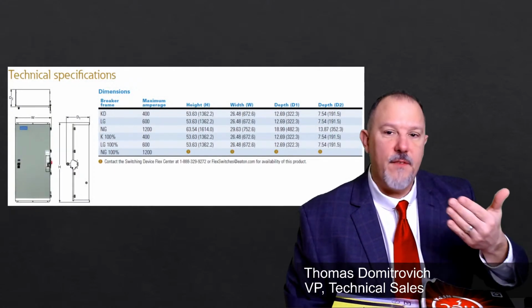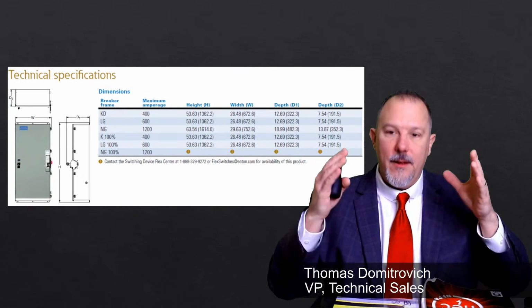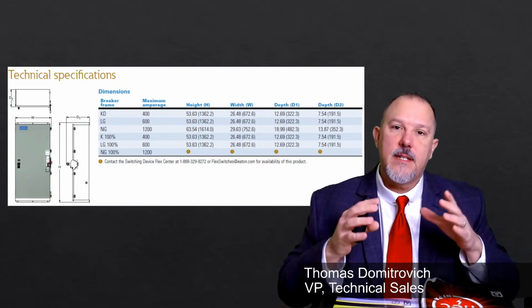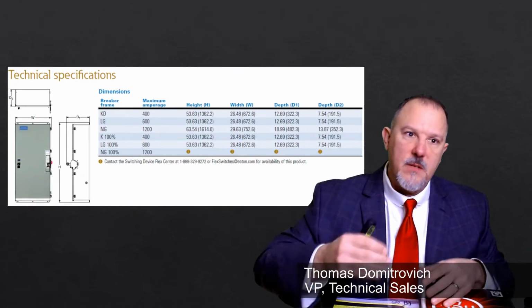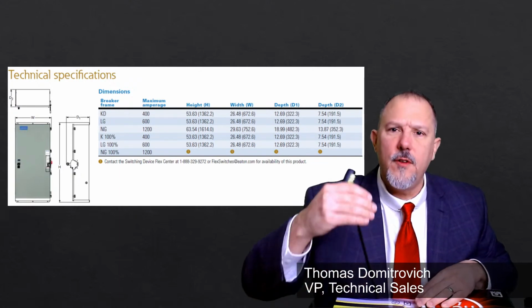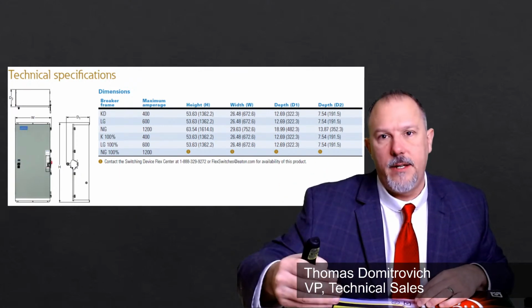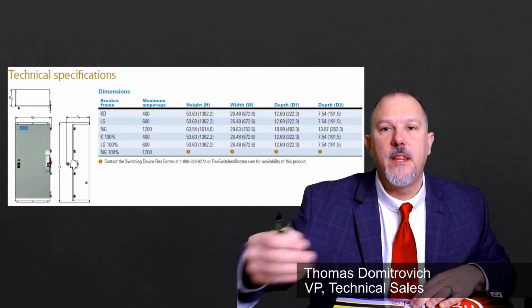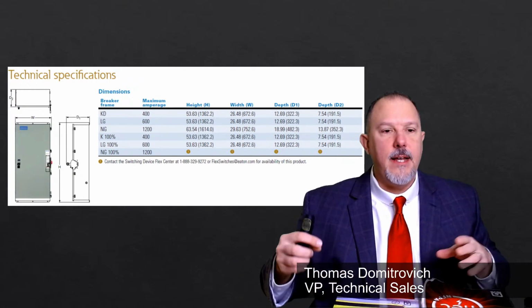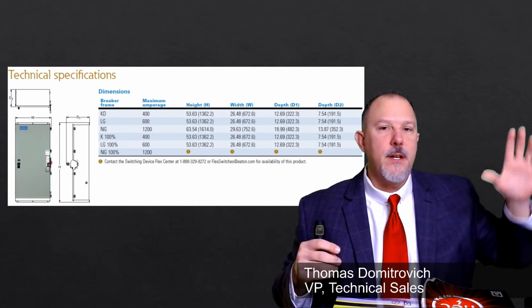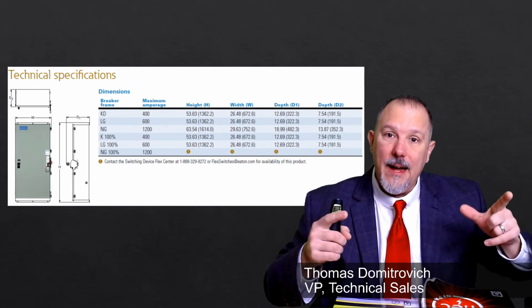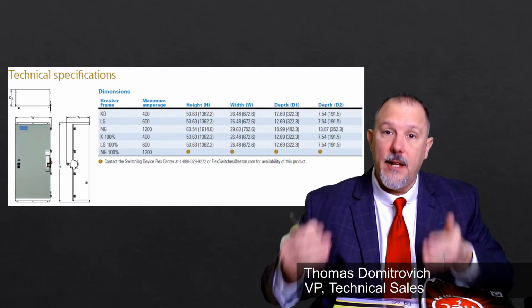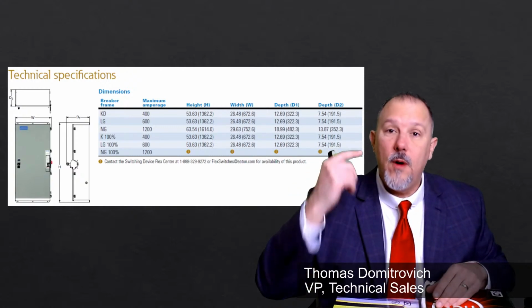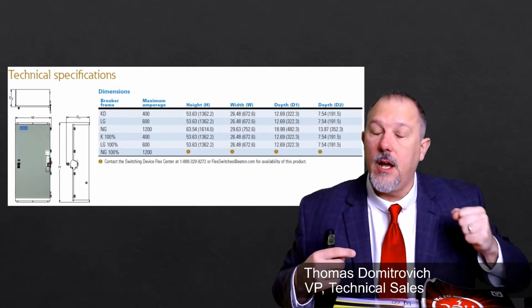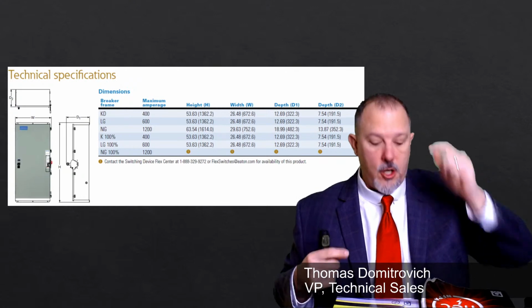All right, we have the enclosure size. The reason I put this in here from a size perspective: put these products as close as you can to the equipment you're trying to provide the protection for, right? If it's a panel board, try to put it next to the panel board. Why? Because we want to facilitate the electrically safe working condition. We want them to pull that handle to the off position. We want them to go through 70E.